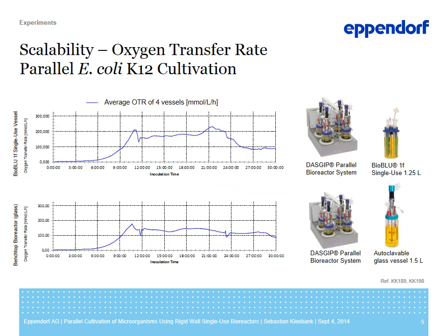On this screen you see the results of the oxygen transfer rates. This graph is an average of 4 bioreactors. In the upper graph you see the BioBLU 1F results. So after the batch we reached oxygen transfer rates of up to 200 millimoles per liter per hour. And after starting the feeding we reached values between 150 and 200. After we decreased the feeding, we also see this in the oxygen transfer rate because the value decreased down to 100.